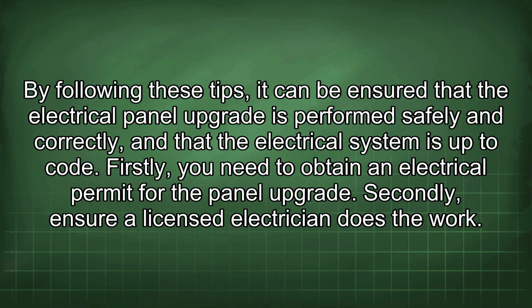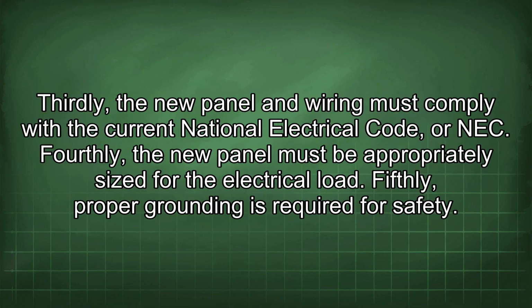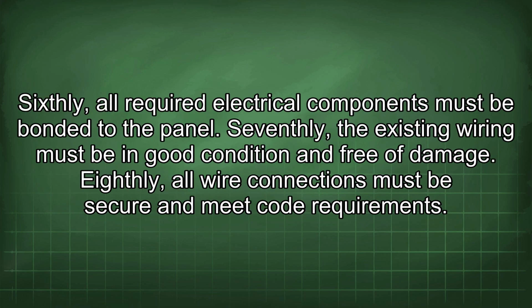Firstly, you need to obtain an electrical permit for the panel upgrade. Secondly, ensure a licensed electrician does the work. Thirdly, the new panel and wiring must comply with the current National Electrical Code, or NEC. Fourthly, the new panel must be appropriately sized for the electrical load. Fifthly, proper grounding is required for safety. Sixthly, all required electrical components must be bonded to the panel. Seventhly, the existing wiring must be in good condition and free of damage. Eighthly, all wire connections must be secure and meet code requirements.